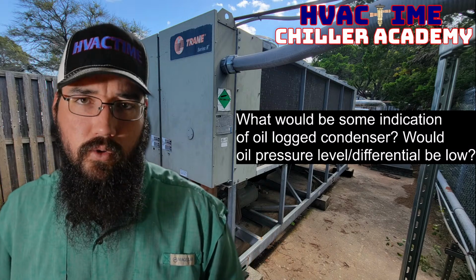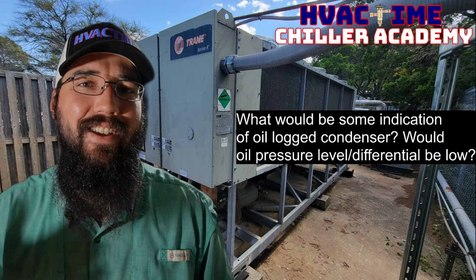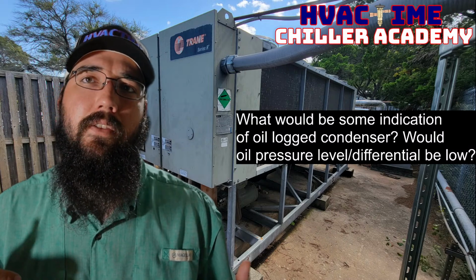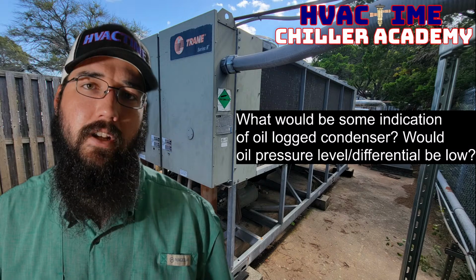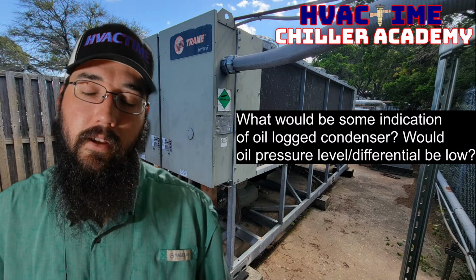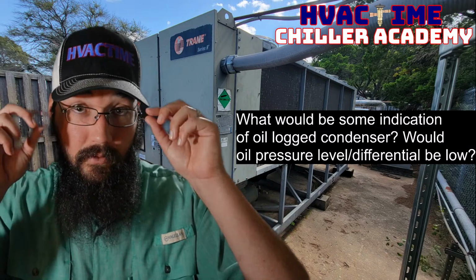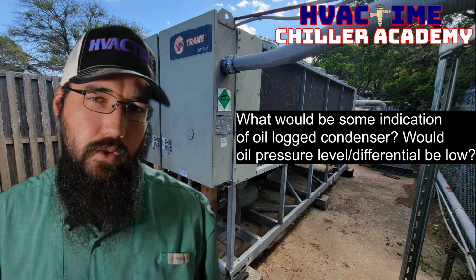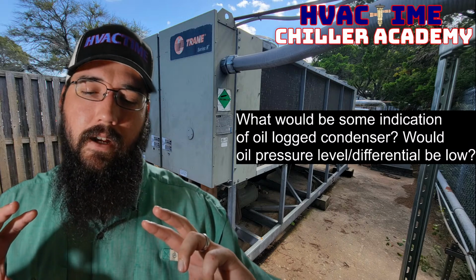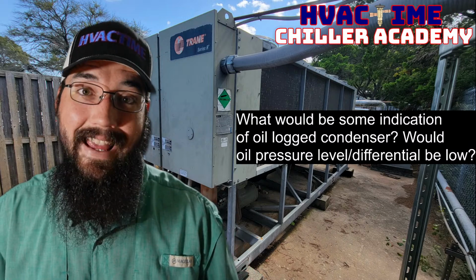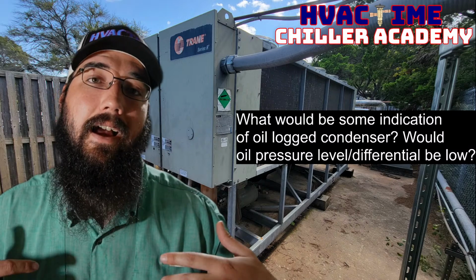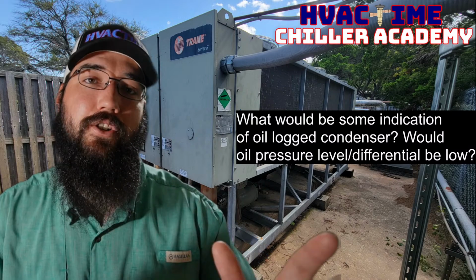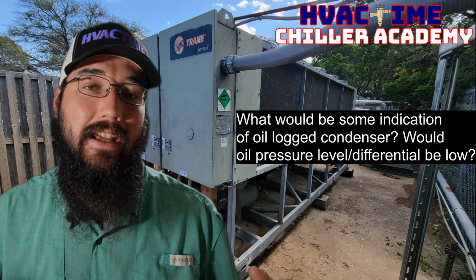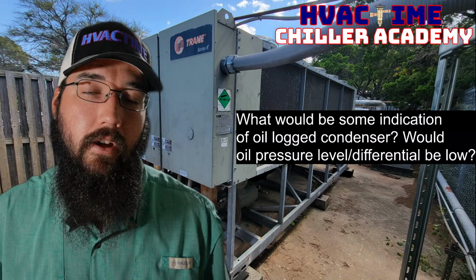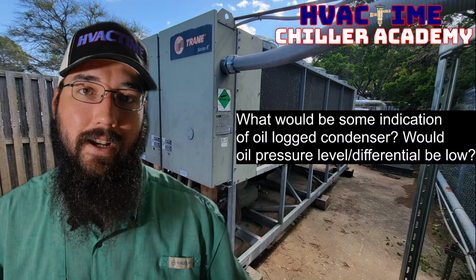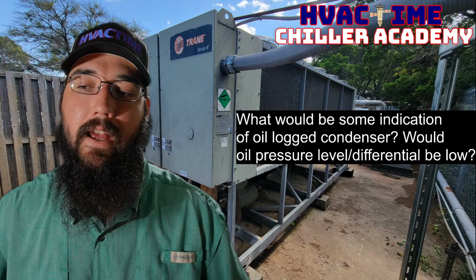And on the water-cooled side, again, if we have excessive oil charge in the system, then I see it gets mixed in with the discharge a lot heavier. The oil separators will struggle. This can happen with centrifugals as well, but it's probably more of a water-cooled screw issue. Either way, the oil separators can't process enough of that oil out. A heavy oil-laden discharge gas gets sent out into the condenser, and that can create a much heavier coating of oil on the condenser tubes as it's draining down.